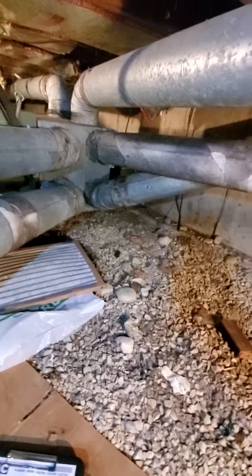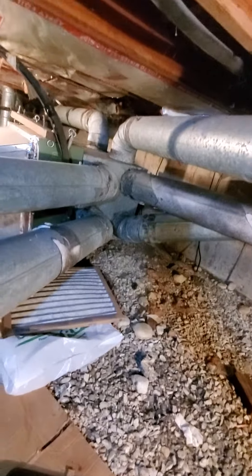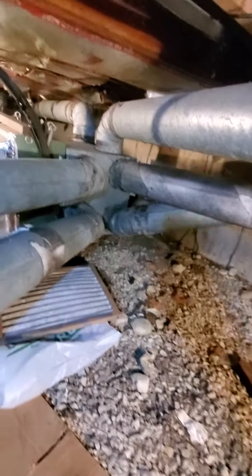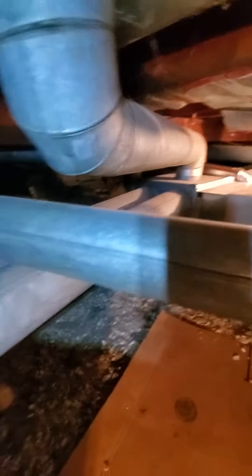This is why I'm thinking we might have to disassemble some flue pipe here, some of that flue exhaust. Those are all your supply trunks, roughly six to seven inches, and you can see how many of those are coming out of there. We're counting about five on this side and I think it was three or four on that side. Same thing with the return.